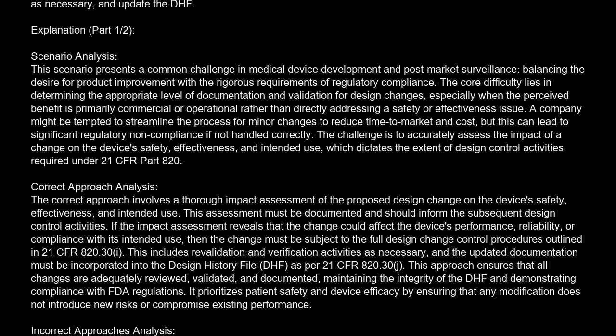A company might be tempted to streamline the process for minor changes to reduce time to market and cost, but this can lead to significant regulatory non-compliance if not handled correctly. The challenge is to accurately assess the impact of a change on the device's safety, effectiveness, and intended use, which dictates the extent of design control activities required under 21 CFR Part 820.